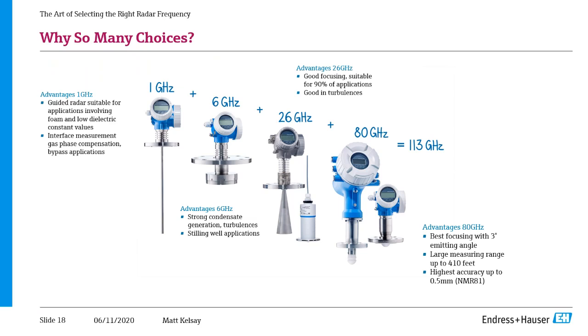So I typically say if you're able to have a probe in contact with the process, you're going to have a more reliable measurement. Really, anytime you can have that, you're just constraining that signal around the probe, and it's going to be a little bit more reliable. That's often not possible due to mechanical forces. Maybe there's an agitator, or maybe there's just the desire to keep everything out of the process if you can. A couple places where you can use a guided radar to make measurements where non-contacting just won't work.